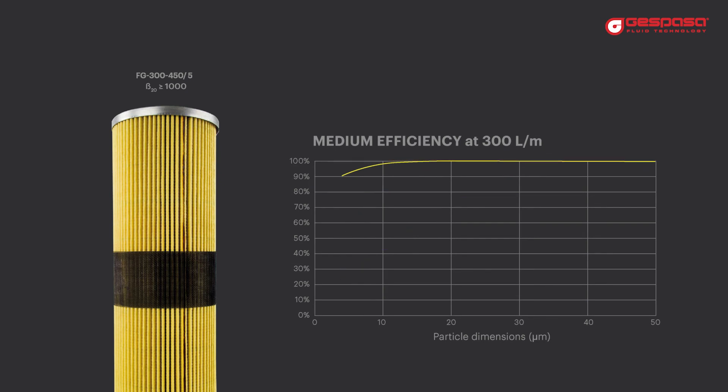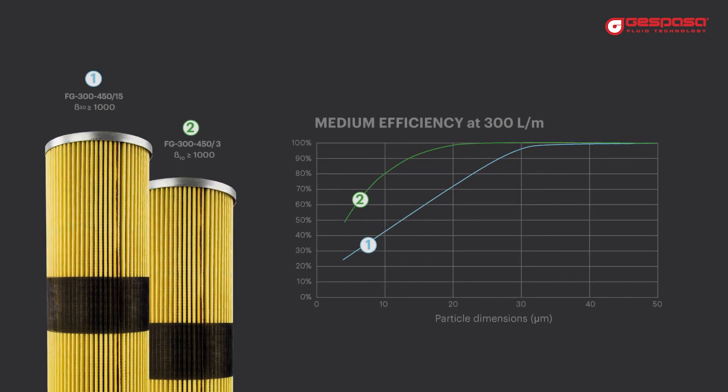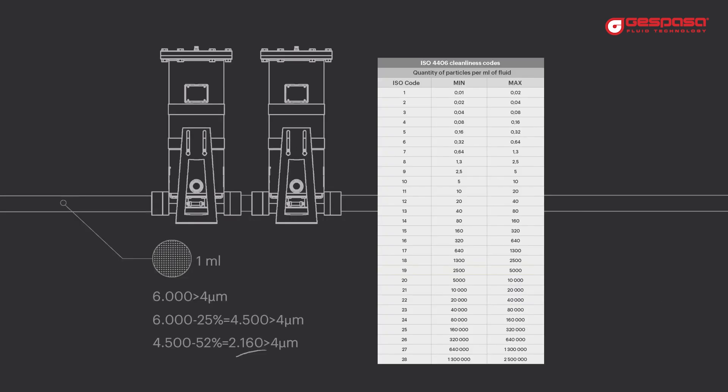If we install a more restrictive filter, we will increase the filtration efficiency in a single pass. As a negative point, the filter will saturate much faster. If we filter in two stages, we will increase the efficiency and prolong the life of the filter elements.